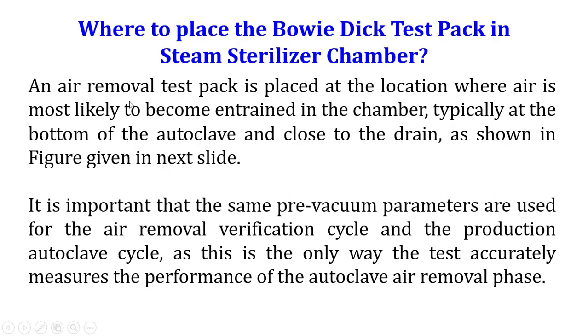It is important that the same pre-vacuum parameters are used for the air removal verification cycle and the production autoclave cycle, as this is the only way the test accurately measures the performance of the autoclave air removal phase. When you perform the Bowie-Dick test cycle, your routine cycle parameters must match the Bowie-Dick test cycle parameters, because if the parameters are different, the air removal efficiency test will not be accurate.